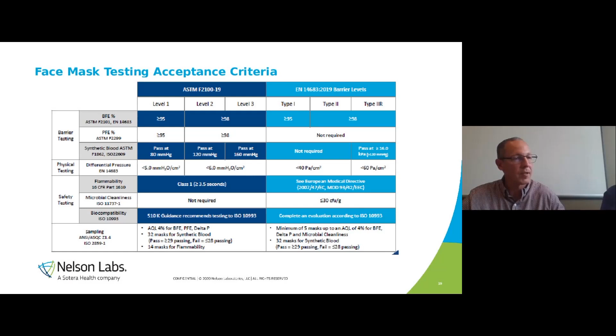Thanks, Todd. We're going to go through this relatively quickly because most of this information here is for your information. But I do want to talk about biocompatibility. When you're looking at face masks, most of the face masks are considered surface devices with prolonged or permanent contact. And so when you're going to the FDA, there's 3 main tests or categories that you have to evaluate for these type of masks. That's cytotoxicity, sensitization, and irritation.